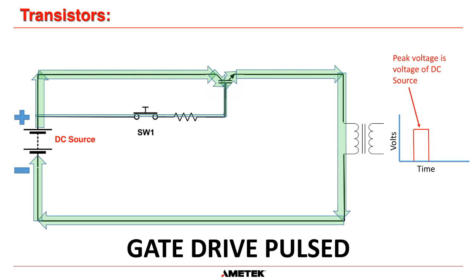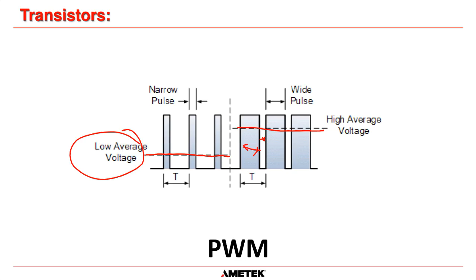We use PWM in our modern UPS systems. That means we can adjust the width of each pulse, which adjusts the width of the off pulse. Similar to the rectifier circuit, if you took a mathematical average of very thin pulses, it would have a low average voltage. But if we widen the pulses, with the off pulses much shorter, the mathematical average is higher. That's exactly what we do with our IGBTs.